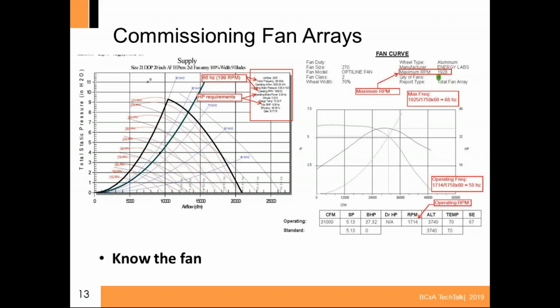That is about 66 hertz. And then on the bottom line, I look over and say, well, they say it's going to operate at 1714. So that tells me that the actual operating point of this fan is going to be right around 58 hertz, if, and the big thing is if, that static pressure on the far right is correct. 31,000 CFM at 5.13 static pressure. I've never known an engineer to leave very much shortage in their static pressure. And I think that's where, if we can know the fan and we help our owner, we can actually help them save energy on these fan walls instead of trying to maintain this huge set point of 5.13. Imagine downstream it's probably supposed to be 1 inch, but that's the total static across the whole system.